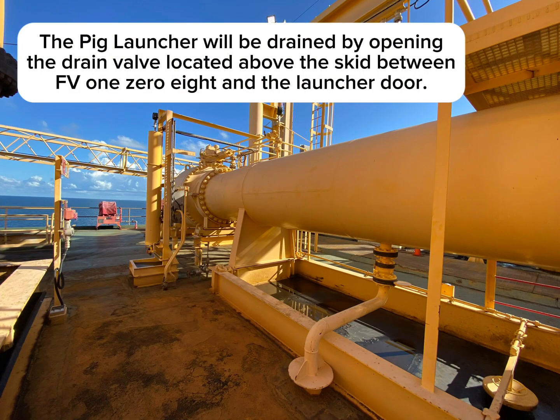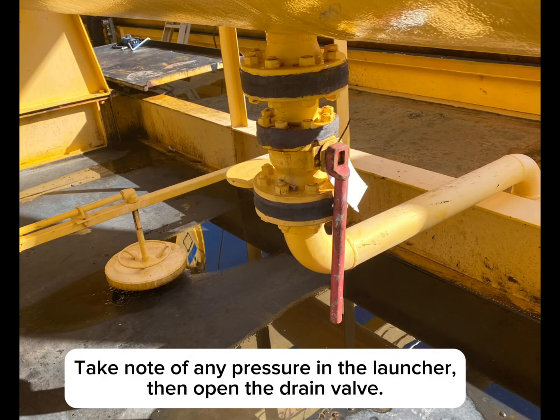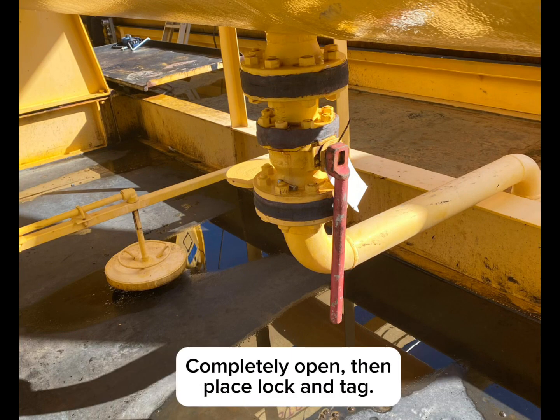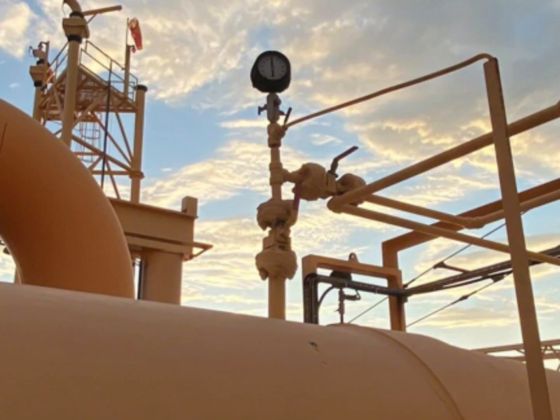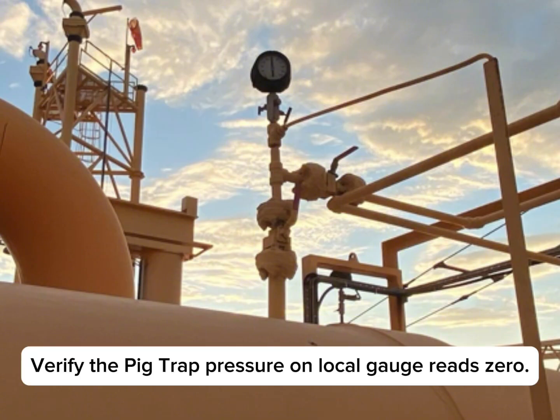The pig launcher will be drained by opening the drain valve located above the skid between FV108 and the launcher door. Take note of any pressure in the launcher, then open the drain valve. Completely open, then place lock and tag. Verify the pig trap pressure on local gauge reads 0.